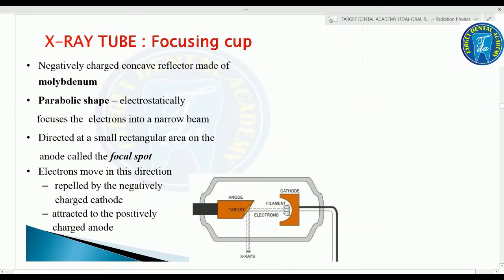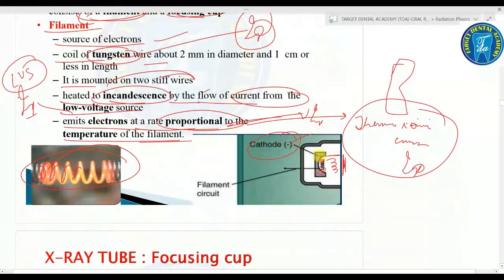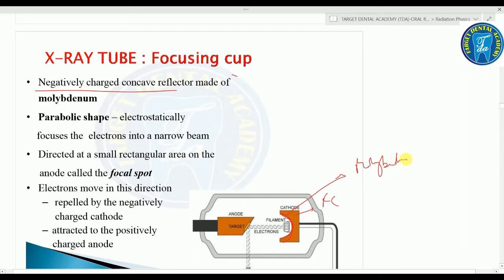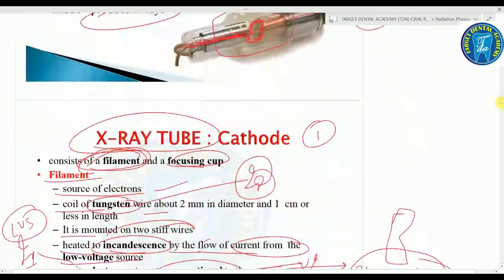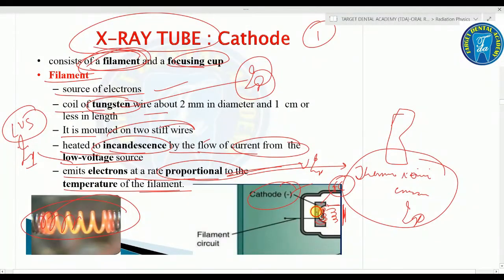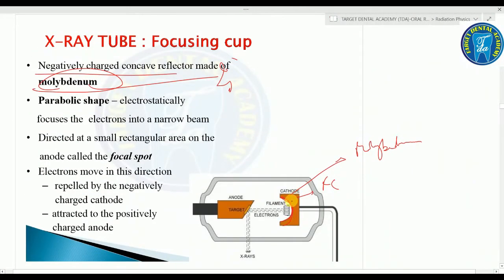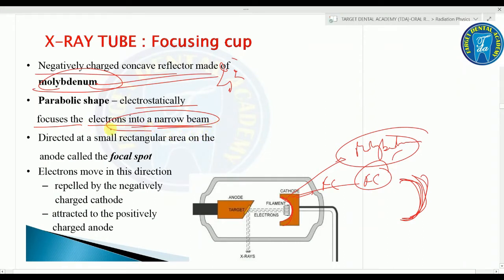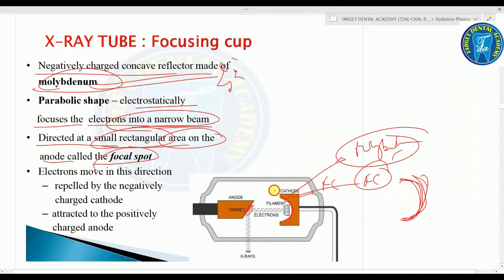The focusing cup is a negatively charged concave reflector made of molybdenum — important: the coil is tungsten, the focusing cup is molybdenum. It has a parabolic shape and electrostatically focuses electrons into a narrow beam directed at a small rectangular area on the anode called the focal spot.